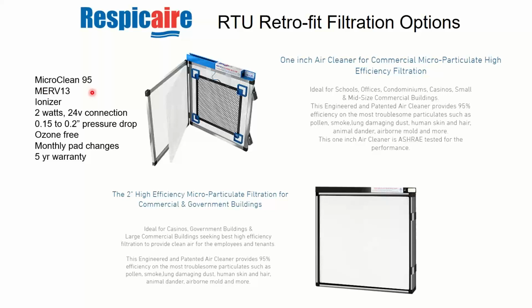This is a Merv 13 filter, but it's only about 1 inch, or 2 inches for the bigger ones, and it has a very low pressure drop, even less than the Secure Air had. So 0.15 to 0.2, like the pressure drop of a normal Merv 10 type filter, or even a Merv 8 in some cases that you may already have. So it doesn't have a lot of pressure drop penalty, but it does require a power connection. It's only 24 volts, which means it's low voltage, so you don't need conduit, making it pretty easy to run power to it.